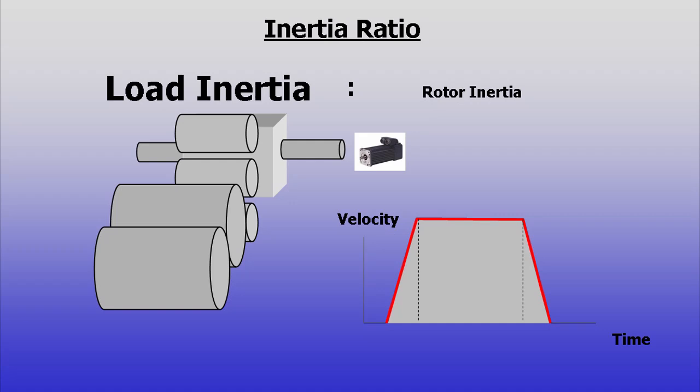The motor may have enough torque to move the load, but it will not be able to accelerate or decelerate quickly, drastically limiting the move profiles that are possible.